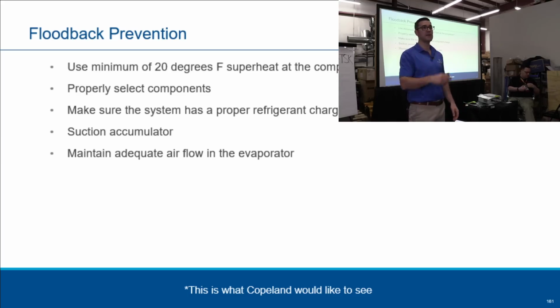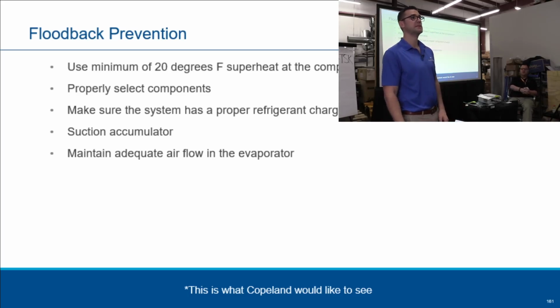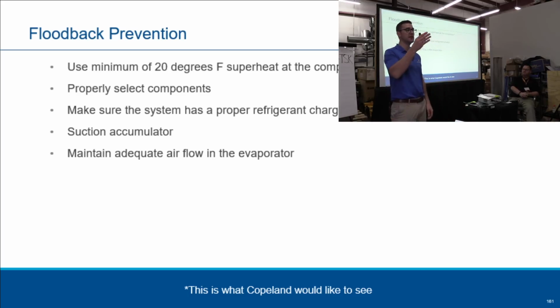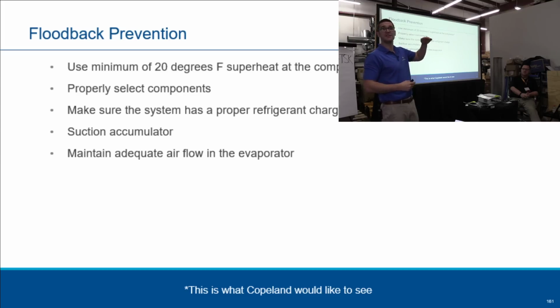Exactly, for semi-hermetic, if you have high suction superheat. Yeah, so that's the best thing. Like Dick, as we talked about earlier, as that suction temperature starts to go up, what happens to your discharge temperature? That starts to go up, right? So as you start getting 40, 50, 60, that discharge temperature is going up, those degrees as well, right? So that's where you want to look. Those are the points that you have to check.